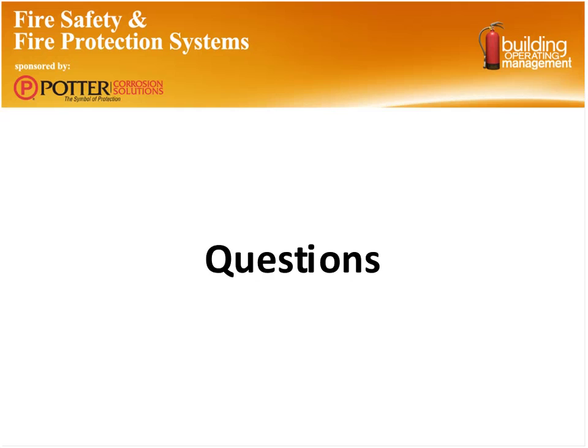Okay, great, thanks. Question, what about polypiping? What are the concerns with that? Polypiping, I guess I don't quite understand that one. The only types of fire systems that we would typically see any kind of plastic piping in are some of your residential type sprinkler systems where we're using a low flame spread or CPVC piping network. Typically some of the orange plastic pipe. Don't really ever see that in fine water mist, that's for sure. Couldn't take the pressure rating. Okay, okay. Is epoxy coating the pipes a good solution to corrosion?